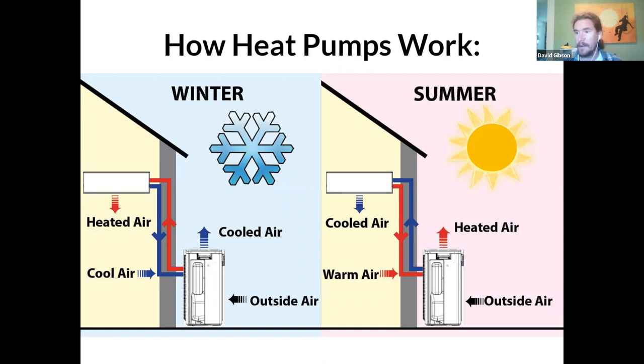The key thing here is that you need to have refrigerant lines and electrical that run between the indoor and outdoor unit. So generally they need to be fairly close to each other. Most manufacturers, you can have 50 or 60 feet of refrigerant line. The longer that is, the more expensive the system is going to be, the more complicated the installation. And so typically, if you can have them on opposite sides of the same wall, that's going to be the simplest and most efficient installation.